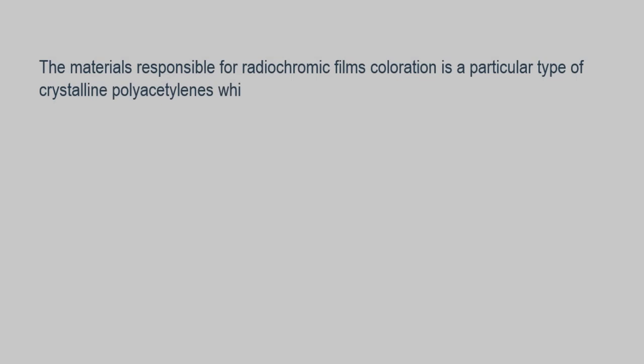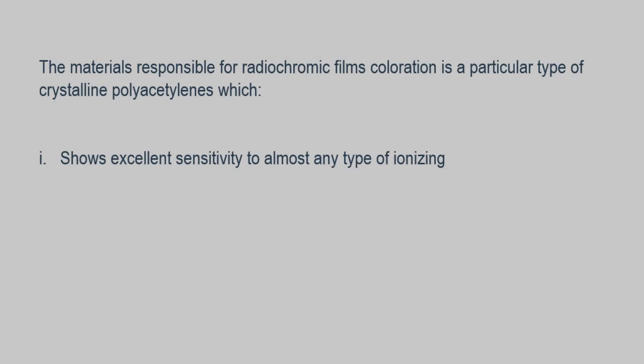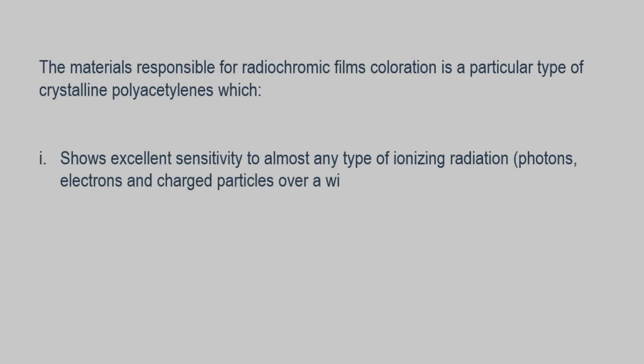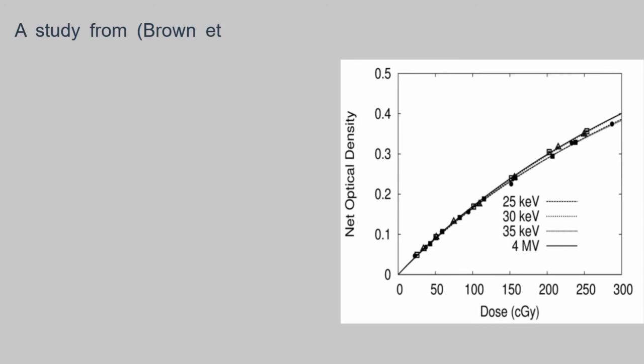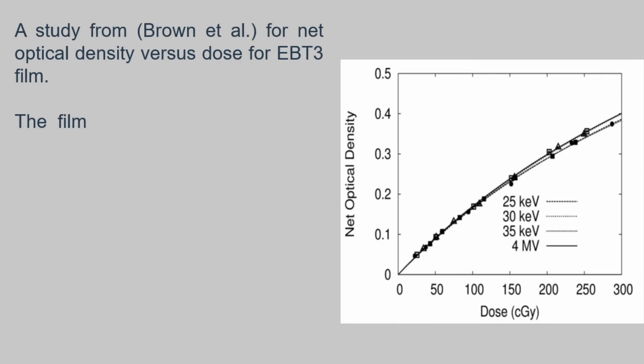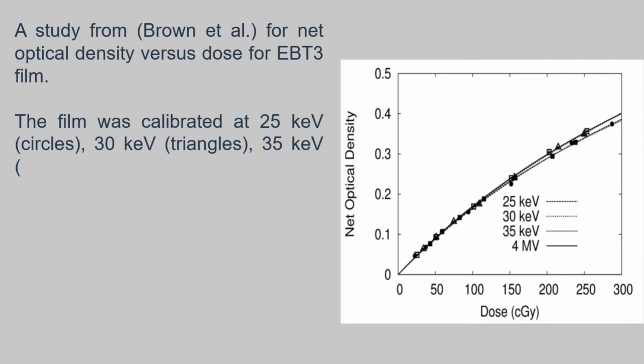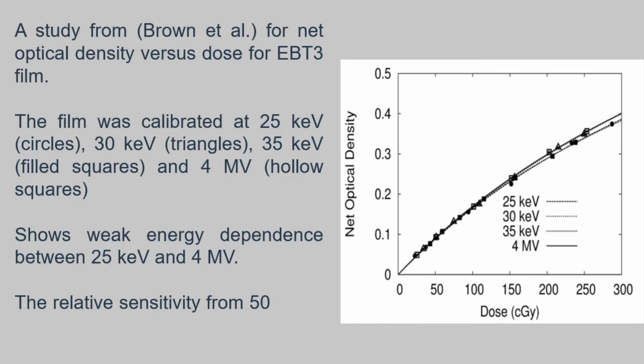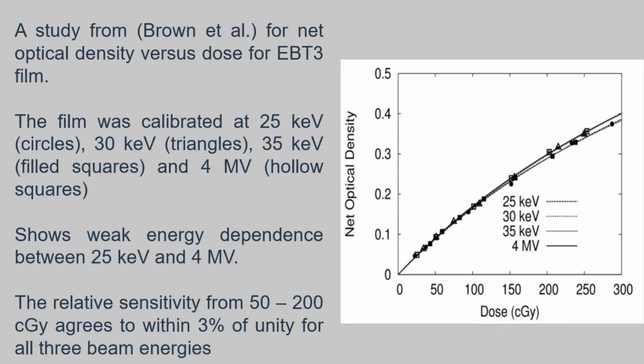The material responsible for radiochromic film coloration is a particular type of crystalline polyacetylene with characteristics including: 1) excellent sensitivity to almost any type of ionizing radiation such as photons, electrons, and charged particles over a wide range of energy and dose; 2) very low sensitivity to neutrons; and 3) almost total insensitivity to room light. A study from Brown et al. found net optical density versus dose for EBT3 film calibrated at 25 keV, 30 keV, 35 keV, and 4 MV. The film showed weak energy dependence, and relative sensitivity from 50 to 200 cGy agreed to within 3% of unity for all three beam energies.